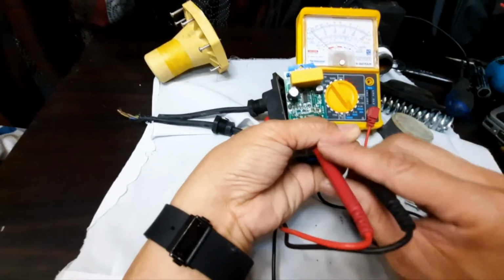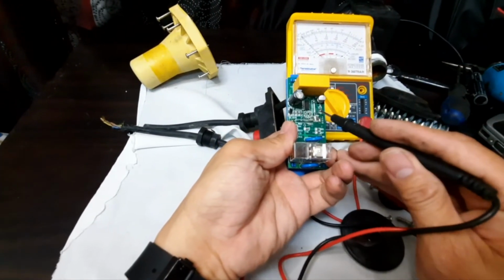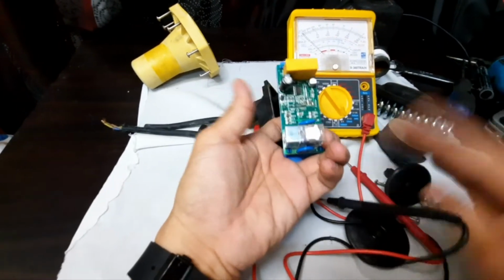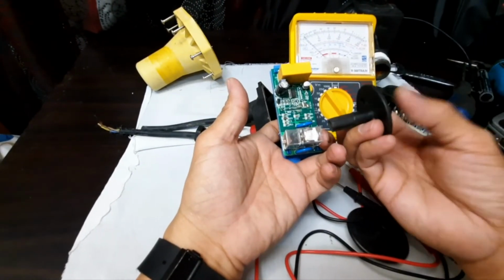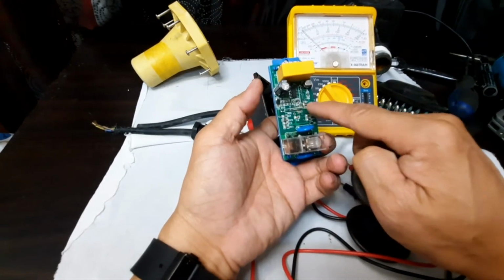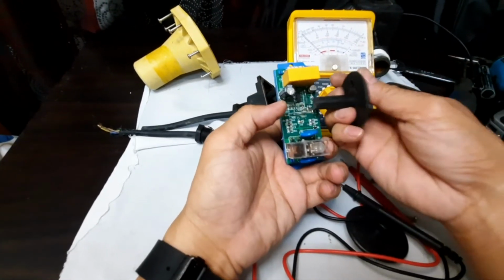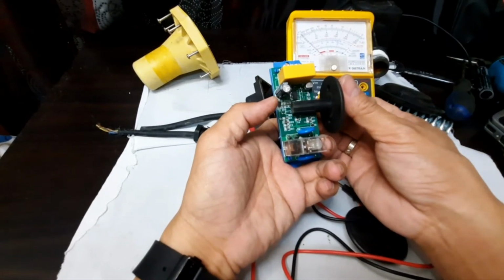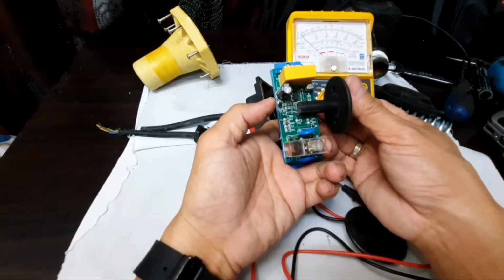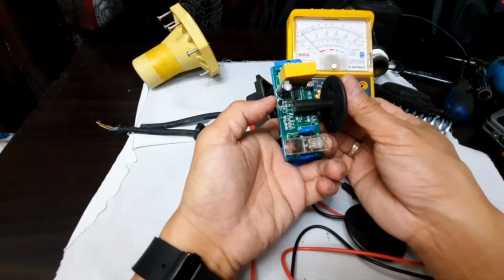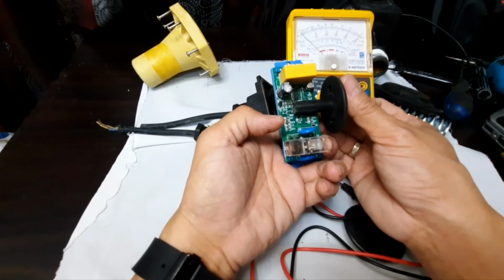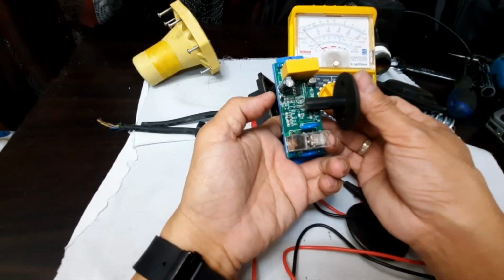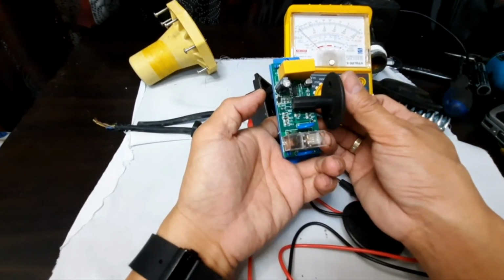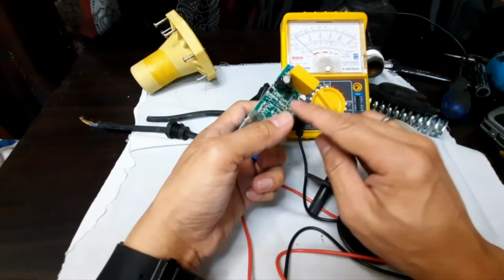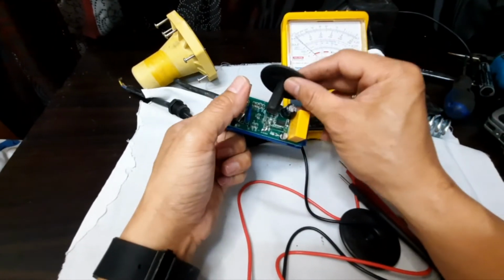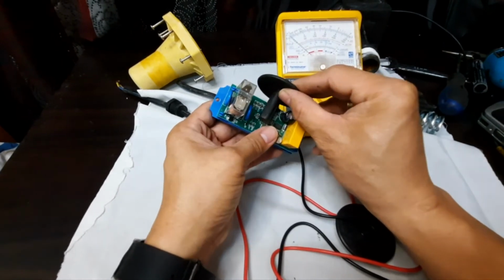Okay, so here we got two sensors, one is here and another one is here. So this is how it works. Magnetic plunger, this is the magnetic sensor. So it senses the plunger if it is high enough or low enough to trigger the pump on or trigger the pump off. And this is how it works, through level or through pressure. Okay, so I hope you understand the simplest way, the electronic way of triggering the pump to turn on and off.